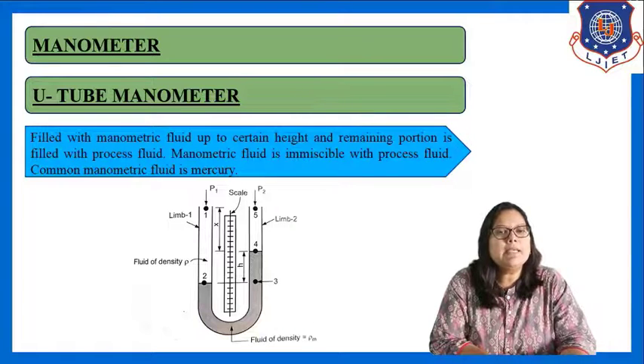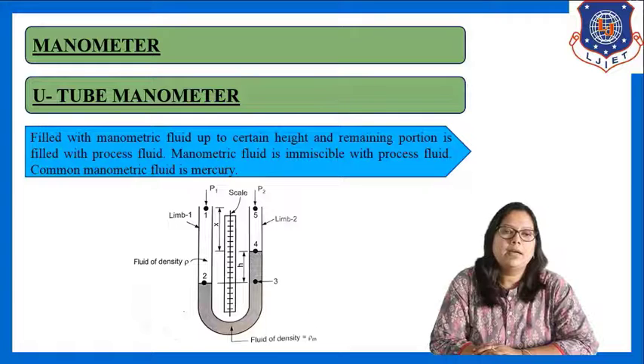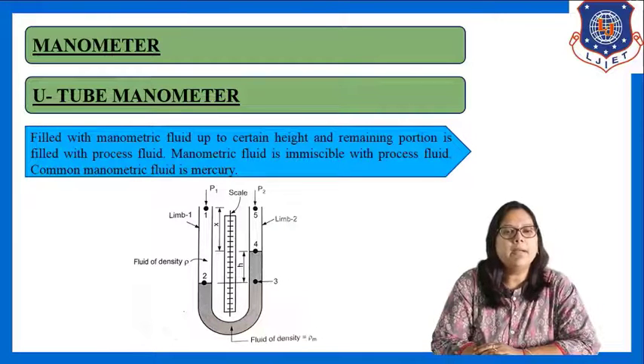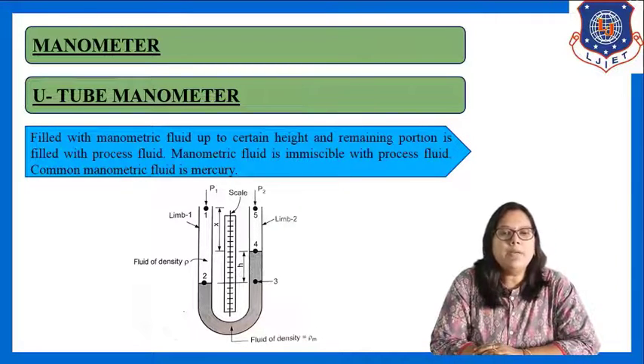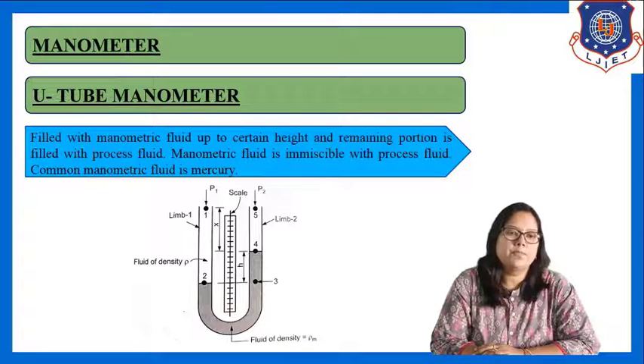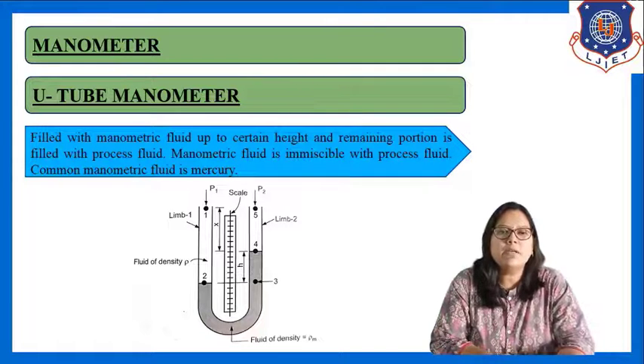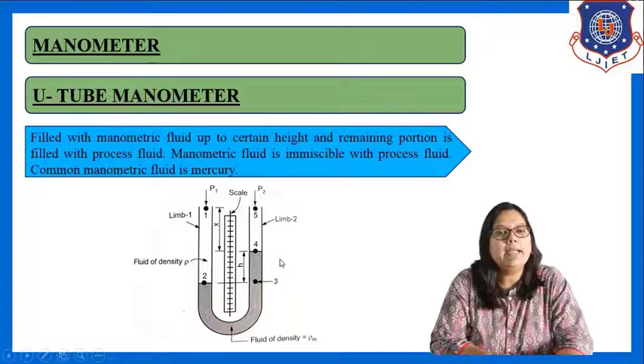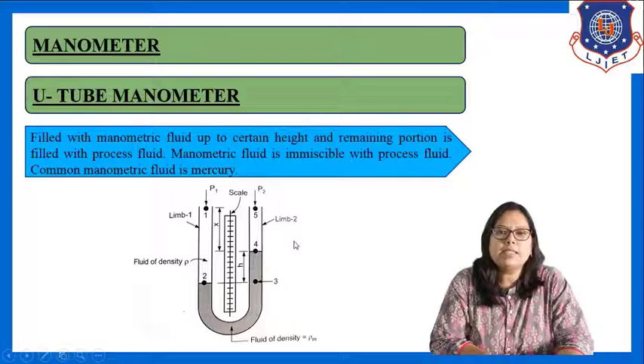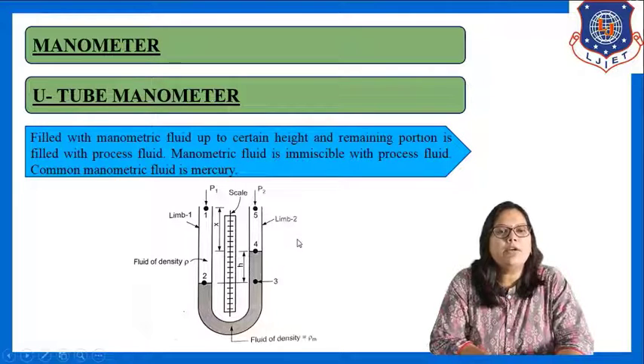What is the basic selection criteria for selecting manometric fluid? The manometric fluid must be immiscible with the process fluid — that is our primary requirement. Because if it is miscible with the process fluid, we cannot easily identify the height difference. The common manometric fluid which is used is mercury.